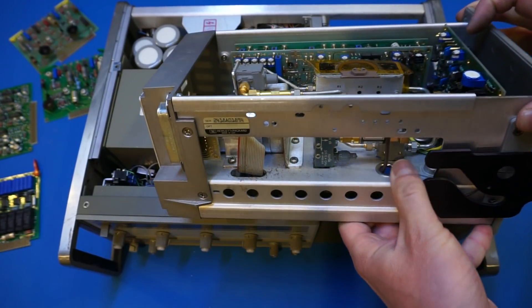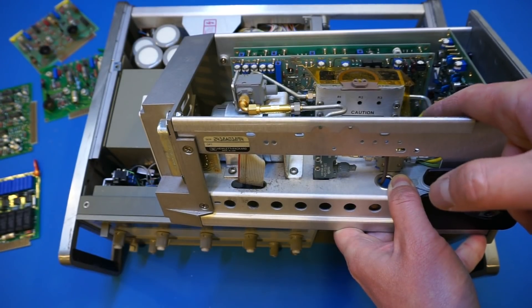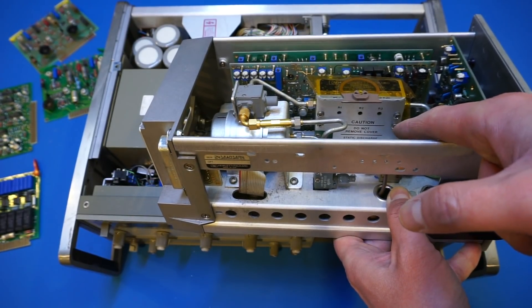This power amplifier is a gallium arsenide field effect transistor based. And it's very sensitive to static electricity. That's why you see here, caution, do not remove cover. Static discharge could cause damage.